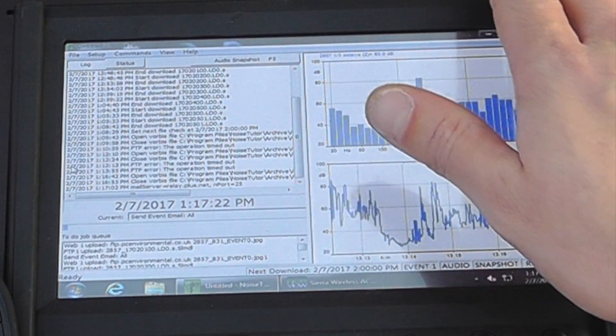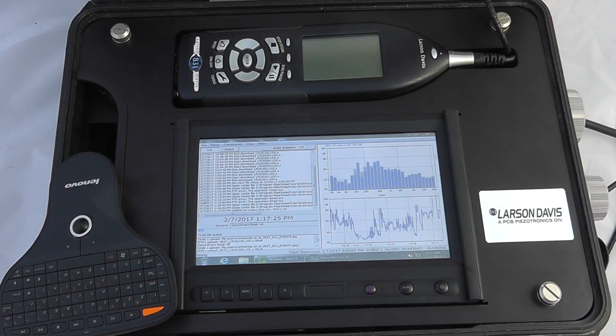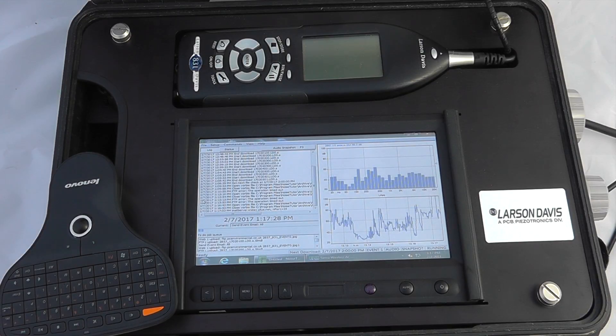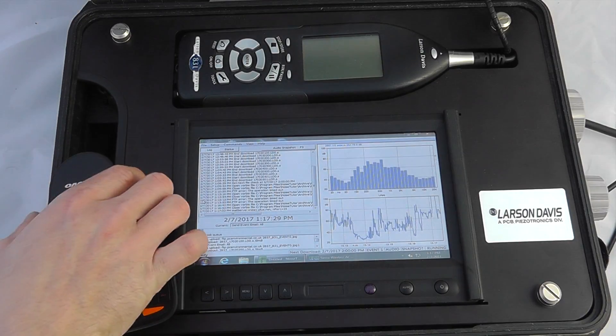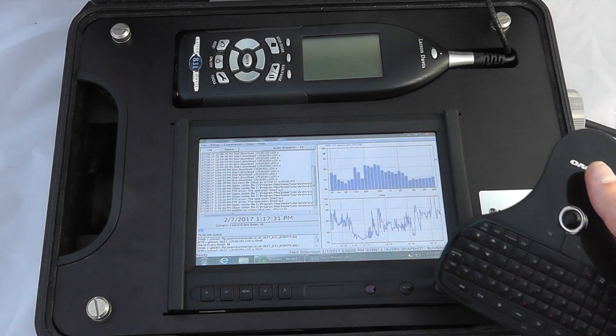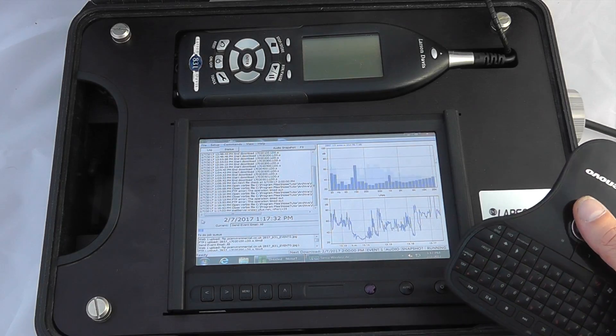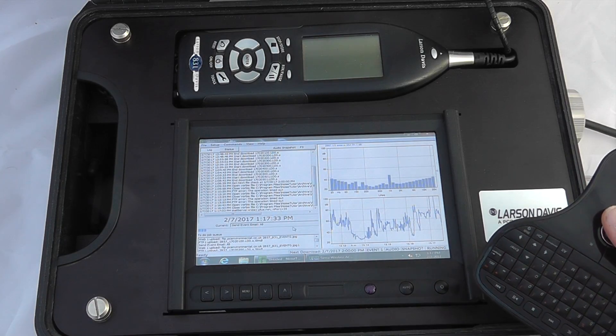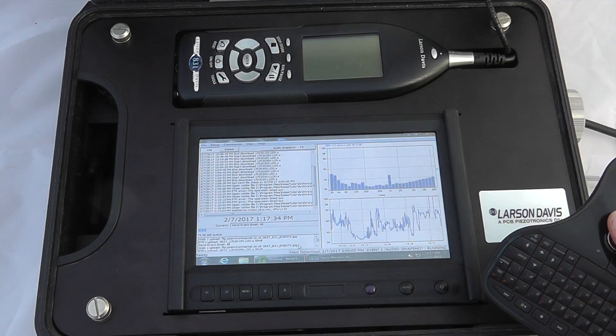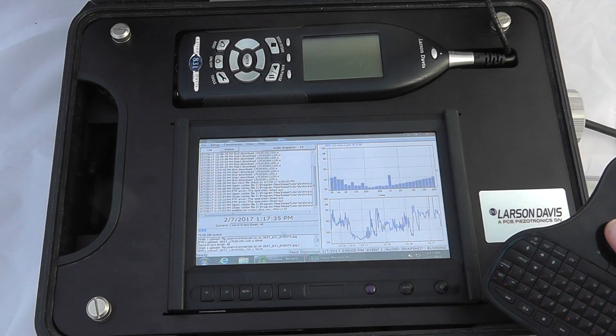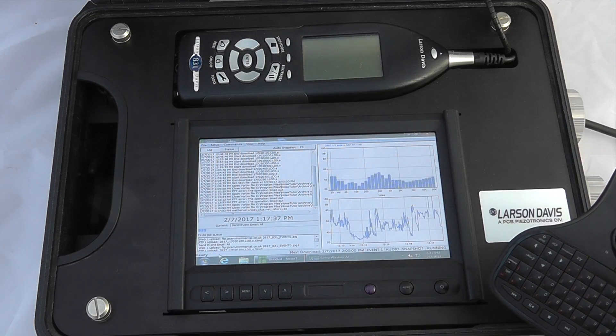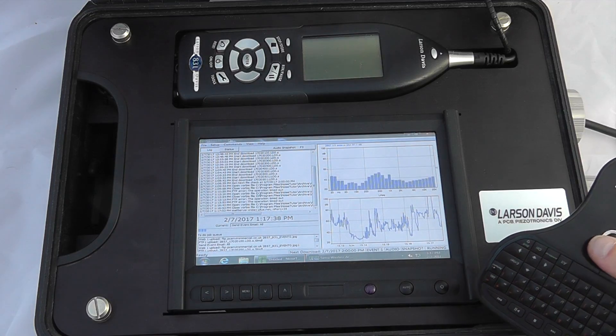This is built behind the main 831 sound level meter. Everything operates as normal. This gives us full remote access to the instrument and we can interface with the device using the full Windows 10 laptop.